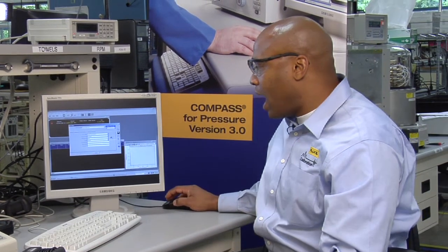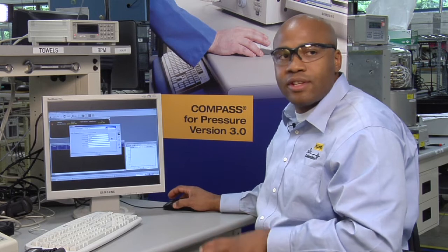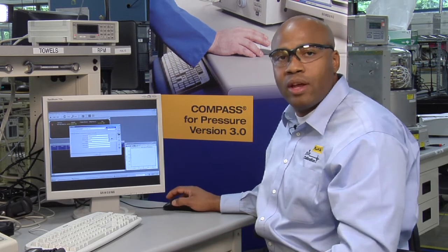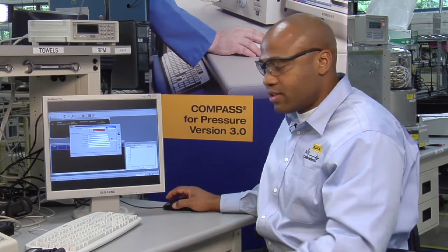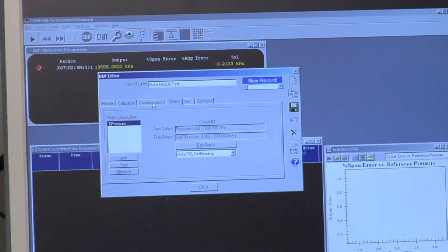By using this option, this will go into the Compass example setup database and load the specifics for this instrument. All the other tabs are now populated with information specific to this pressure module.